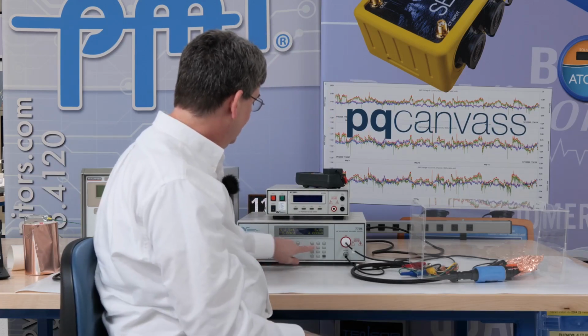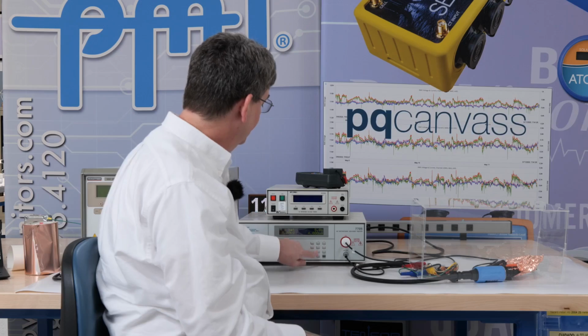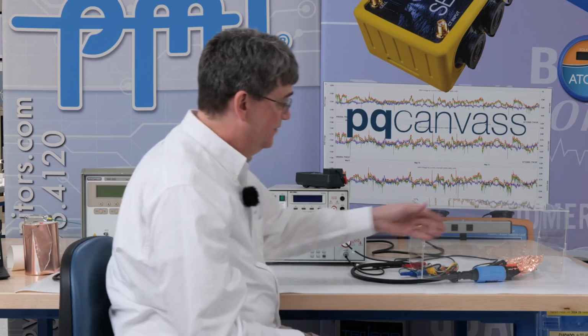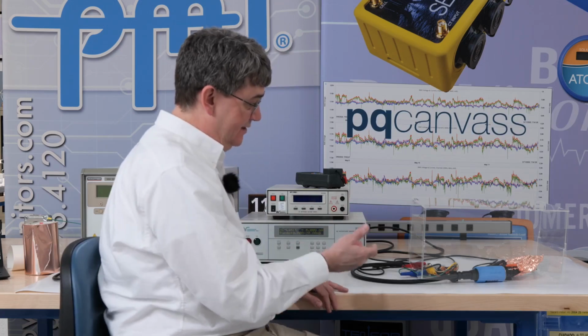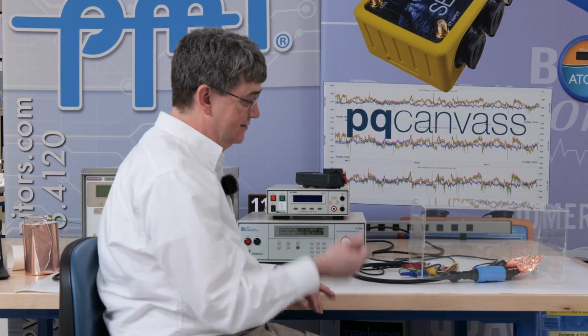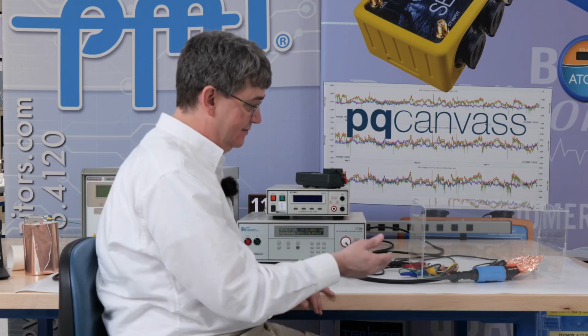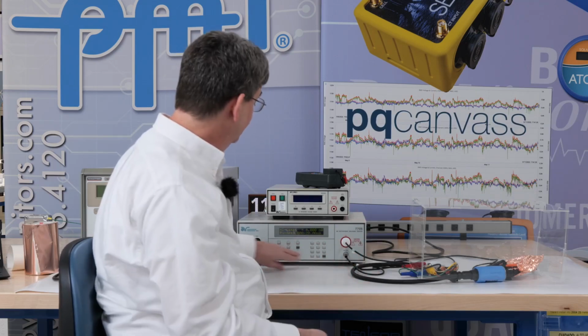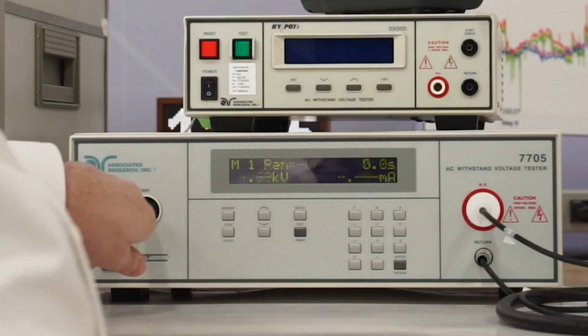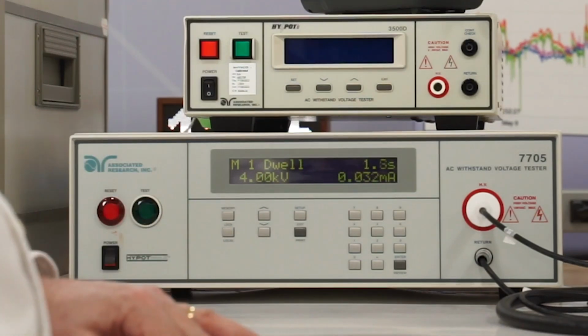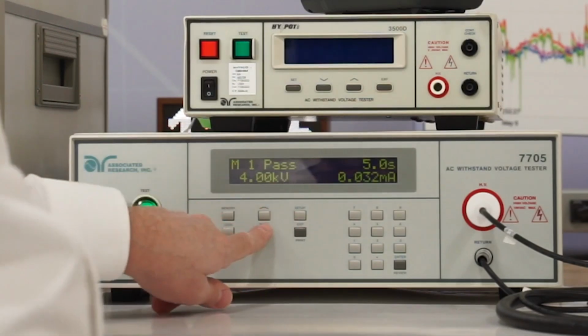All right, we're going to start back at 4 kV. And here we have the foil connected around both the flexible CTs themselves and the cable that connects the flex CT elements to the bolt, in case you're holding either one of those. We easily pass at 4 kV with 32 microamps.